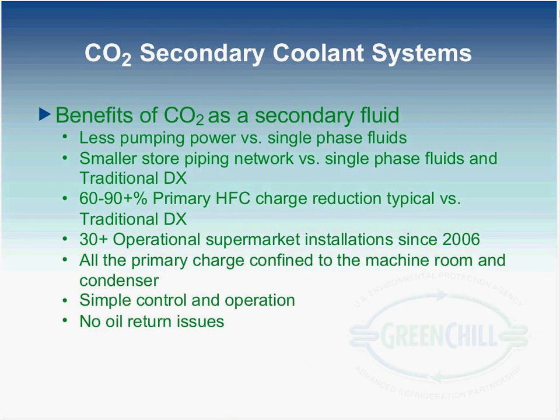Benefits of using CO2 as a secondary fluid: there's a lot less pumping power compared to a single phase fluid like glycol. Usually the flow rate is about 1/10 for CO2 of that of a glycol system. This saves on the piping network. The piping network is much smaller than glycol, and it's even smaller than traditional DX systems. Rule of thumb is the supply and return lines are one size smaller than traditional DX. On average, you save at least 60%, and you can go even higher than that depending, like I said, on what you do with the condenser on the system and the heat reclaim. There are 30 of these stores operating throughout North America. The first one in North America was in 2006. And like we talked about before, all the primary charge is confined to the machine room and the rooftop condenser if you're using an air-cooled condenser.